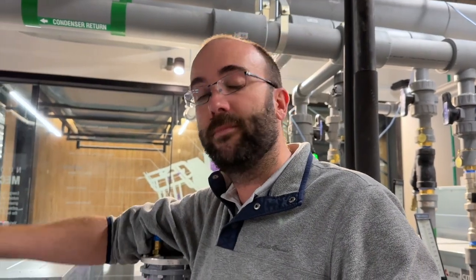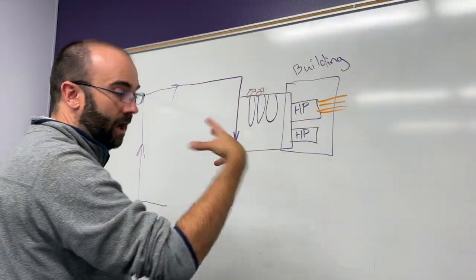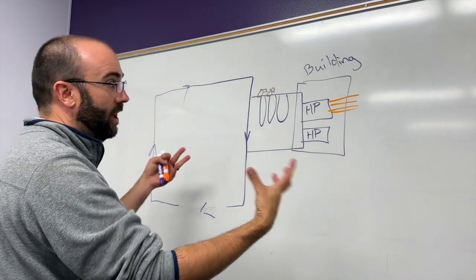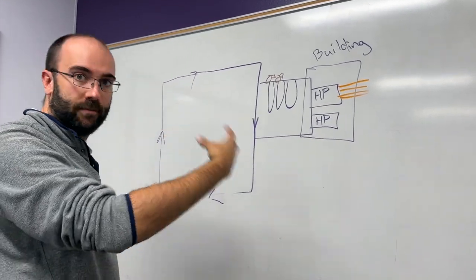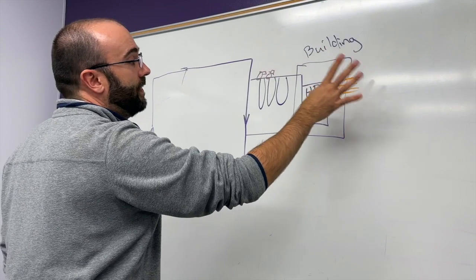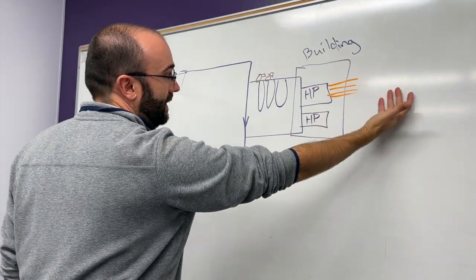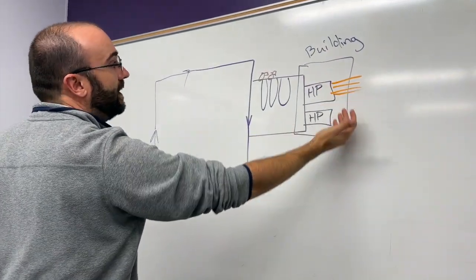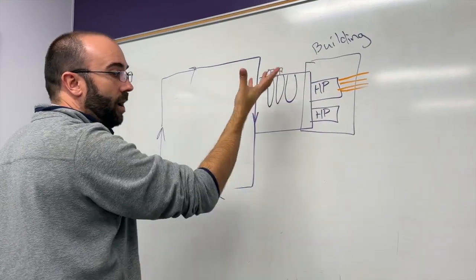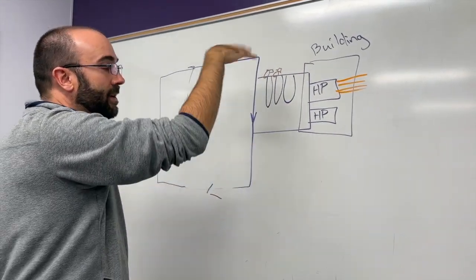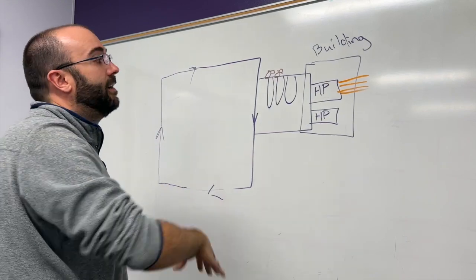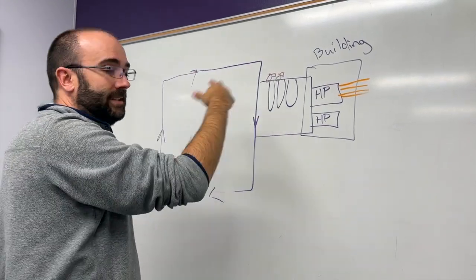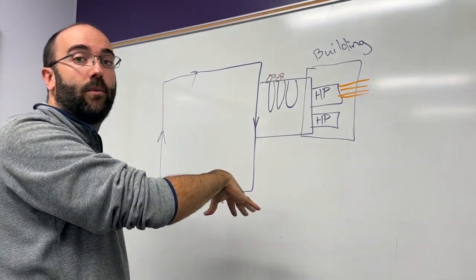How does it work in the summer? We're moving energy from the deep earth into our buildings during the winter, and from our buildings into the deep earth during the summer. It's 110 degrees outside, the building wants to heat up, we have lots of people, lots of computers and equipment. So the heat pumps remove that heat, it goes through the refrigerant lines and into the water, warming it up. Once the water gets warm enough, our deep earth temperature is about 55, so if my water's 70, I can send it underground and cool the water that way.